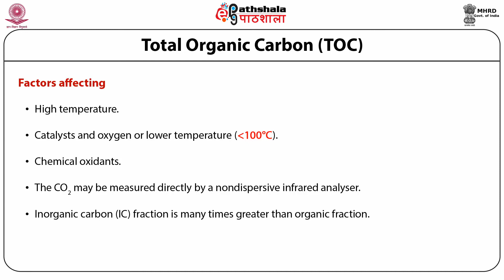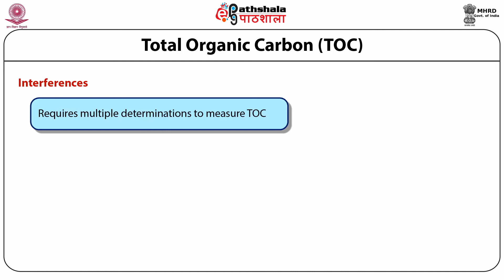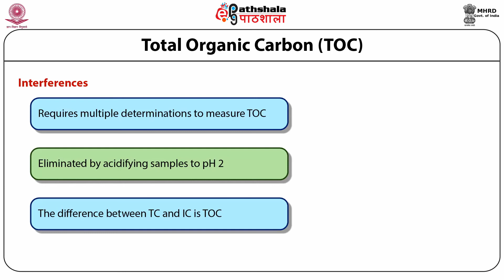In most water samples, the inorganic carbon fraction is many times greater than the organic fraction. So eliminating or compensating for inorganic carbon interferences requires multiple determinations to measure total organic carbon. Inorganic carbon interference can be eliminated by acidifying the sample to pH 2 or less to convert the inorganic carbon species to carbon dioxide. The difference between the total carbon and the inorganic carbon is the total organic carbon.